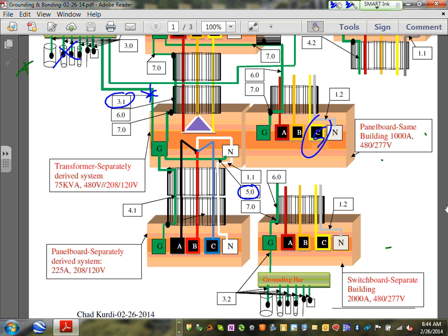Number 5, it's called the system bonding jumper. Can you guys see that right here? The system bonding jumper bonds the new neutral that you created. You just created a new neutral for the 208/120. You are to bond the neutral that you created for the 120 to the grounding electrode system inside the transformer. That's exactly like the main bonding jumper, except it's inside the transformer. This number 5 is called the system bonding jumper. It's not the main bonding jumper. It's the system bonding jumper. Okay, so that's number 5.